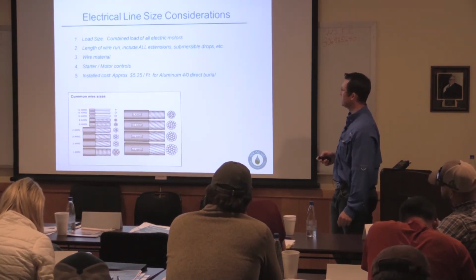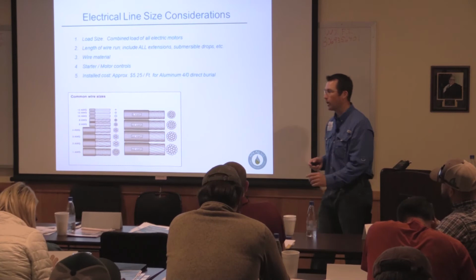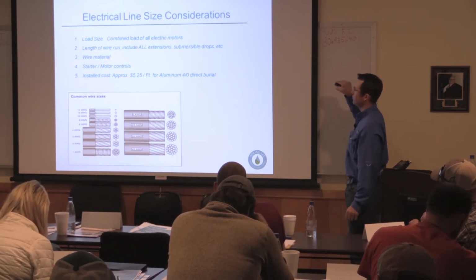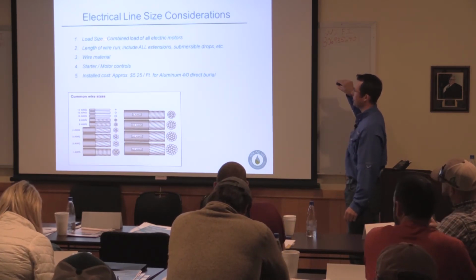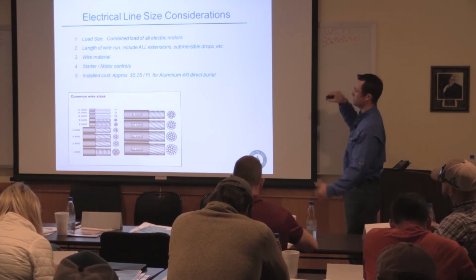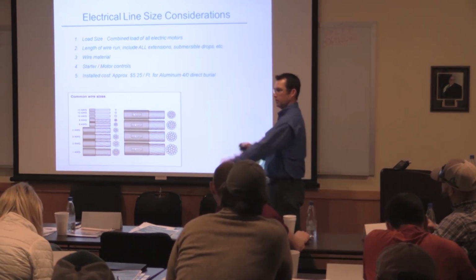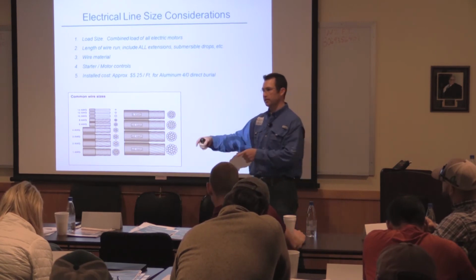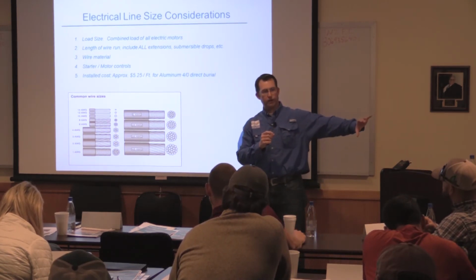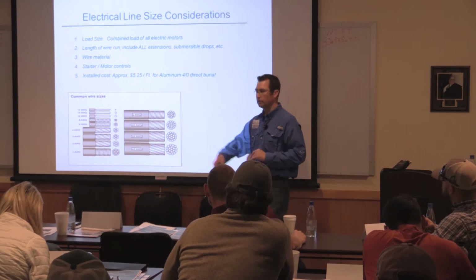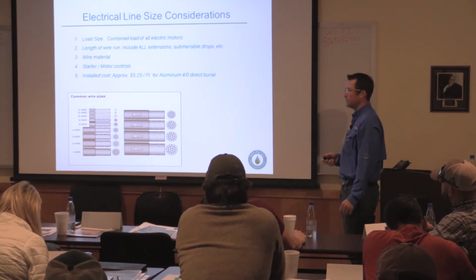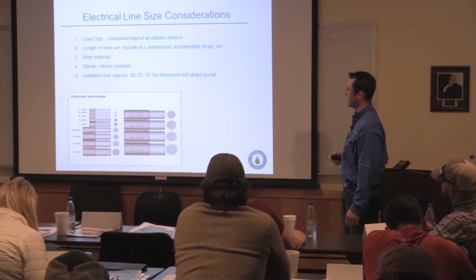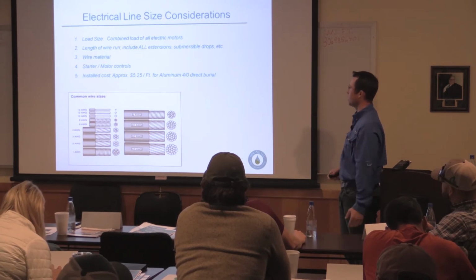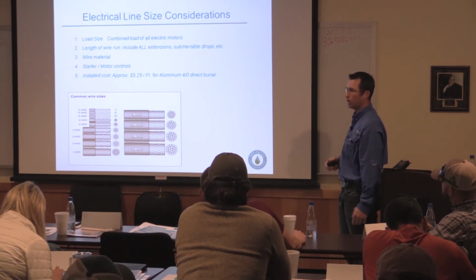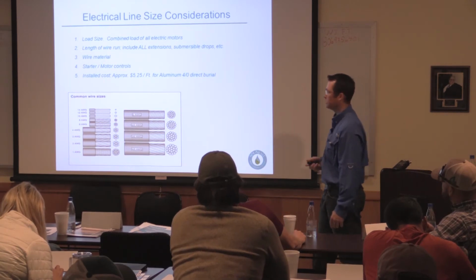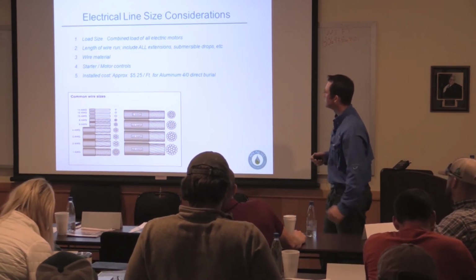We'll step into electrical line sizing. This is the next part of it that's quite important. Again, when you're looking at the load size, you need to combine all of the electrical motors that are going to be down that system. So you can't just get it to one motor and then to the next motor, the next motor. You need to look at it. Do I have enough wire taking it for my entire system from here? These are just considerations we're going to make in sizing. Again, I'd recommend you visit with an expert on this. You can do your research to see if you're in the ballpark, but you really ought to work with the dealer on doing this, or whoever's providing you these products.